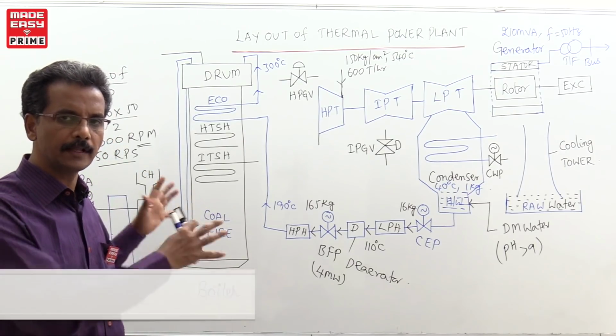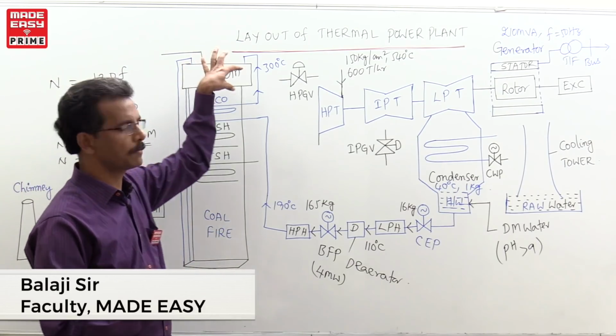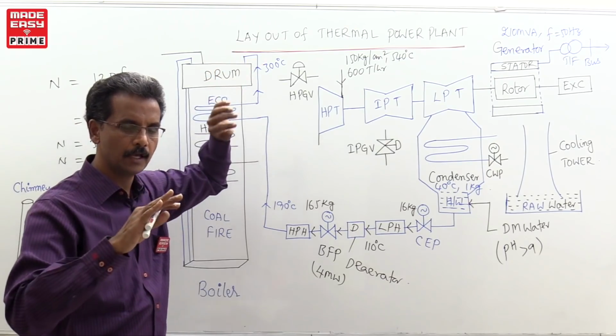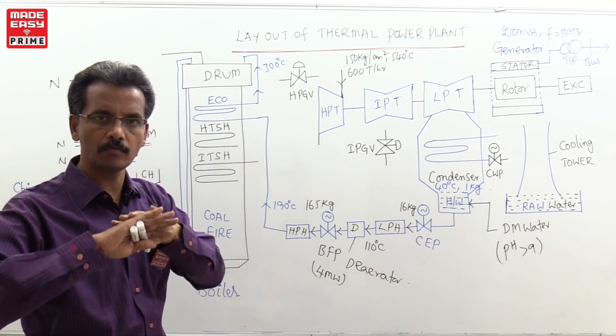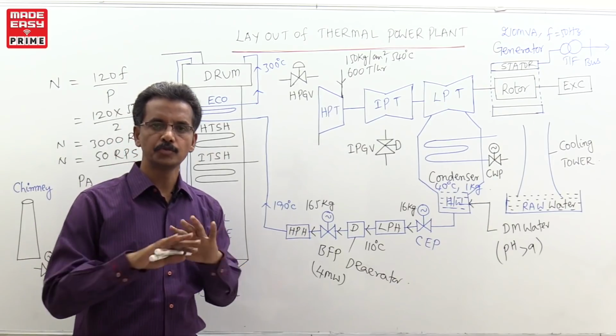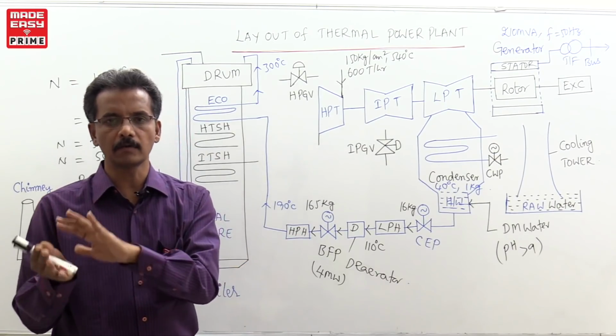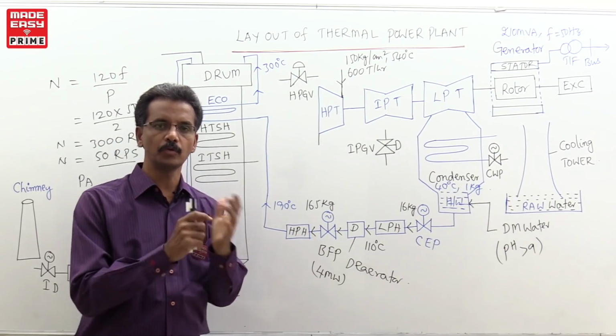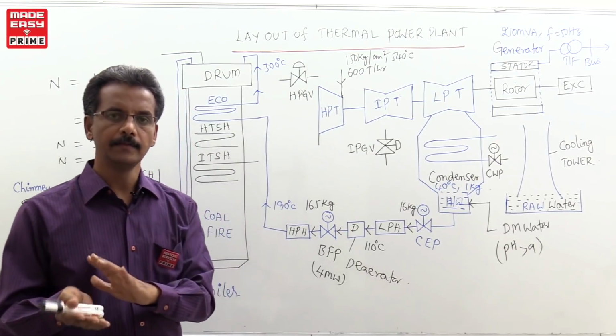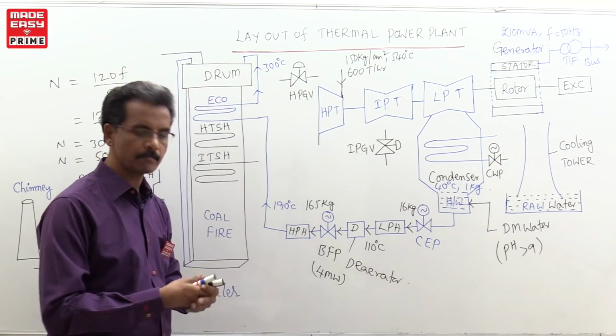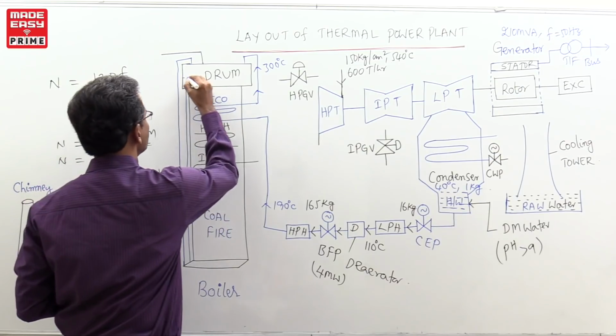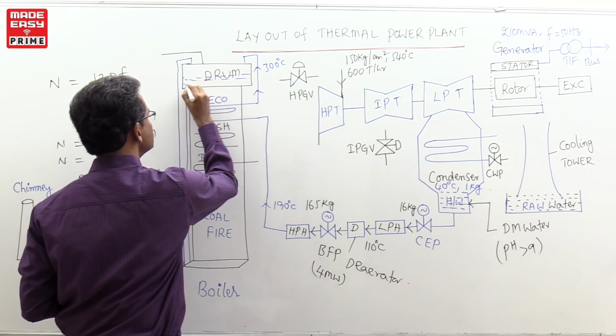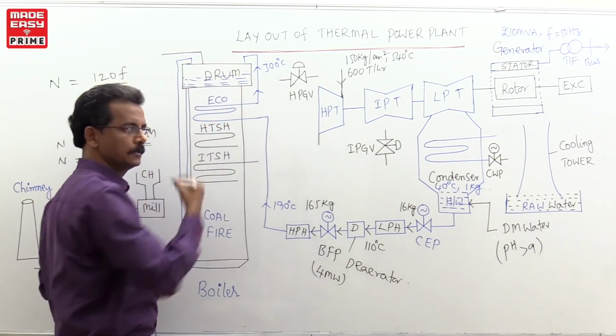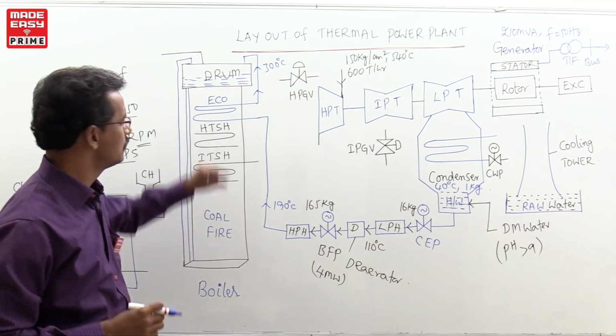Subcritical boilers have a drum. Supercritical, I am repeating, does not have the drum. In the supercritical, they convert water into steam directly without using a drum. But in subcritical, they use a drum. Inside the drum, they send the water. So, now the water is there. The drum is filled with water, not completely. The drum is filled with water up to a 50% level.